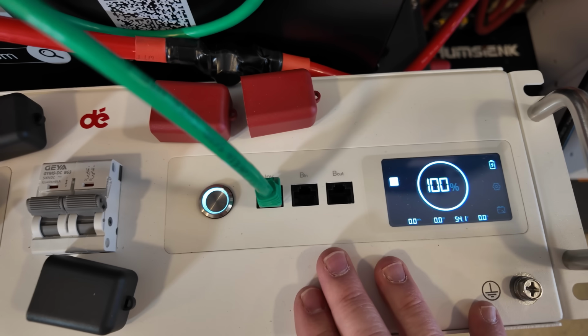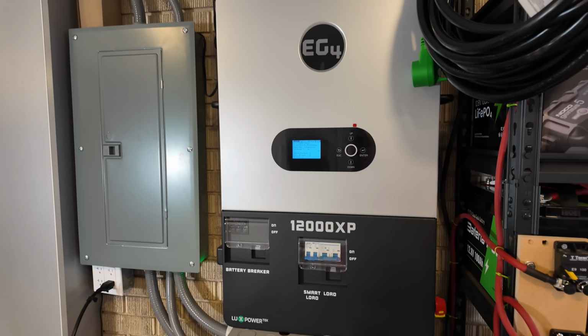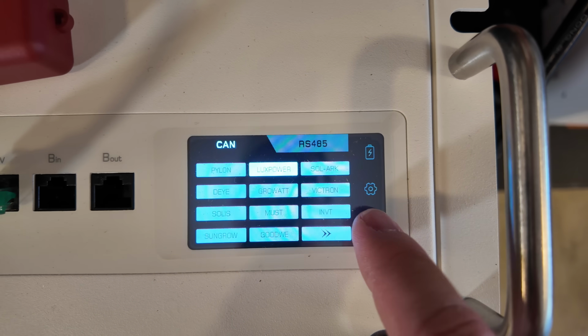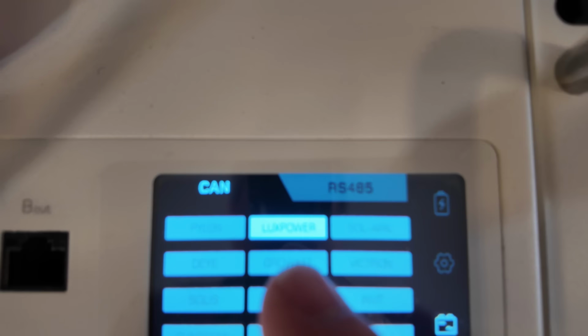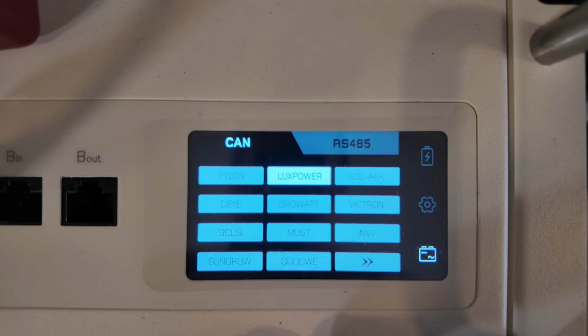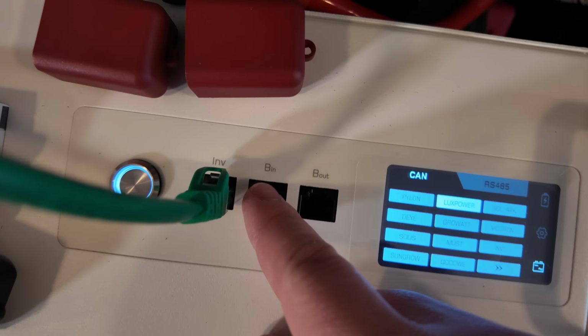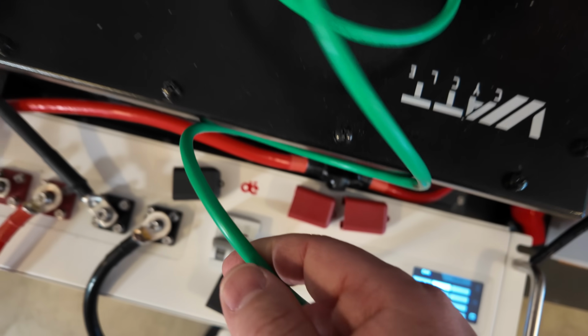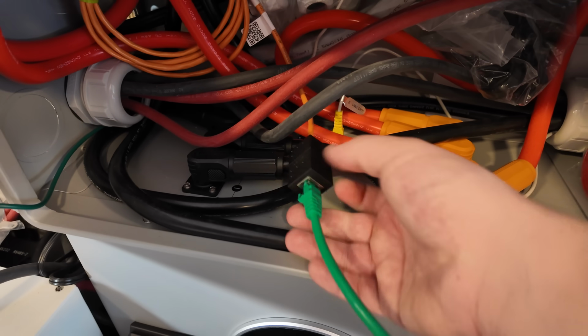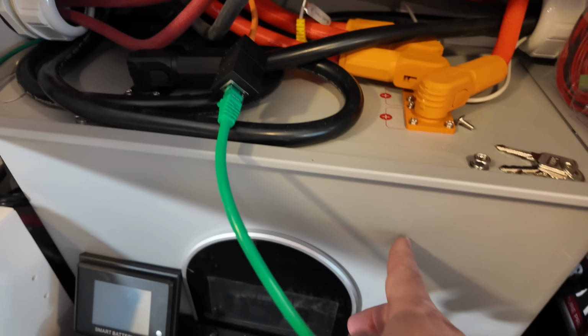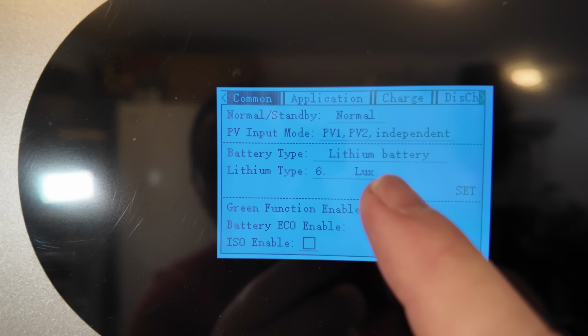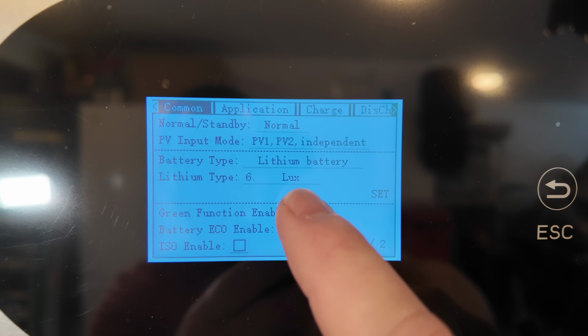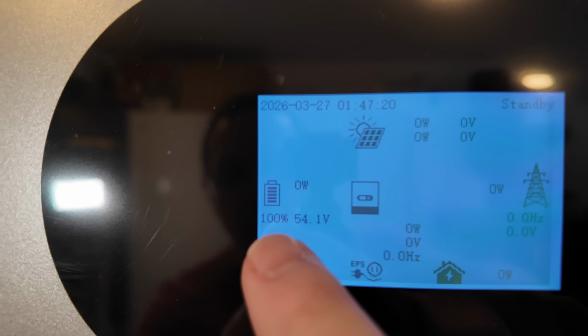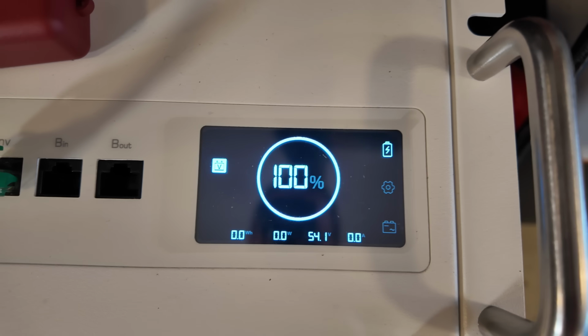Let's test internal communication with this battery and my 12,000 XP EG4 inverter. First, we'll tap this battery icon right here, and we're going to use the CAN protocol, and we're going to use Lux Power. It's a little hard to read in this camera, but Lux Power. Then you can see here in the inverter plug, I've got this communication cable coming up, and I've just spliced into the cable that is normally going to this wall mount battery, and that's going to come up here to the 12,000 XP. And you can see here in the 12,000 XP, I've set it to lithium battery Lux. And you can see we've got communication. This says 100% state of charge, and down here on the battery, we've got 100% state of charge.